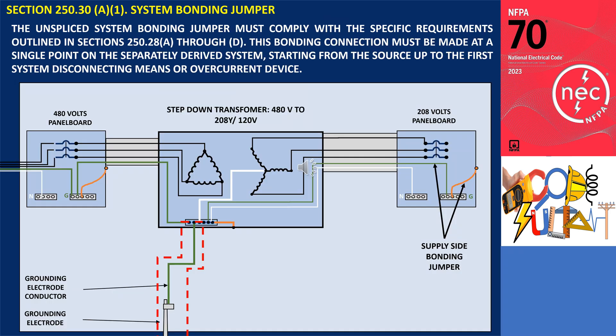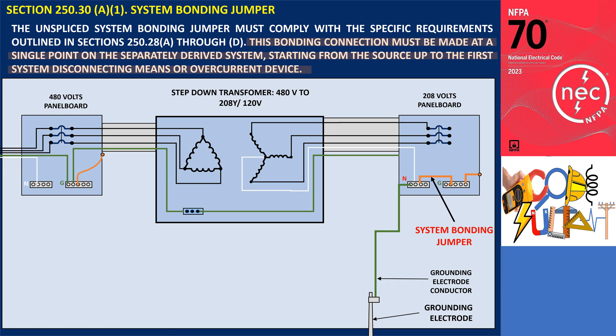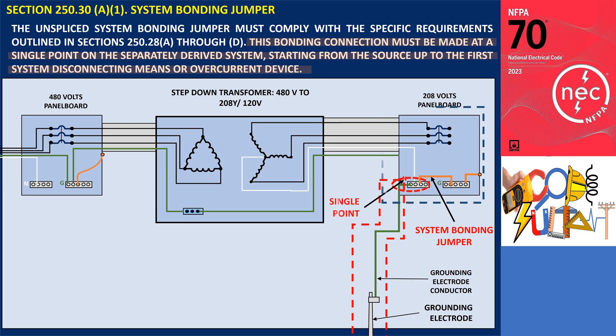The system bonding jumper connection must be made at a single point on the separately derived system. This single point is established as the connection for the grounding electrode, which connects the equipment grounding conductors to the grounded circuit conductors. This connection is specifically installed at the separately derived system, as shown in the illustration. In another illustration, the system bonding jumper is located within the first disconnecting means or overcurrent device of the separately derived system. Further, the location of the system bonding jumper and the connection to the grounding electrode conductor must occur at the same point.